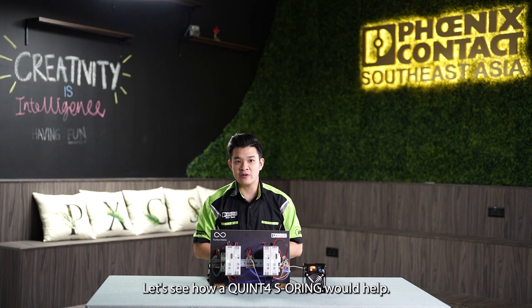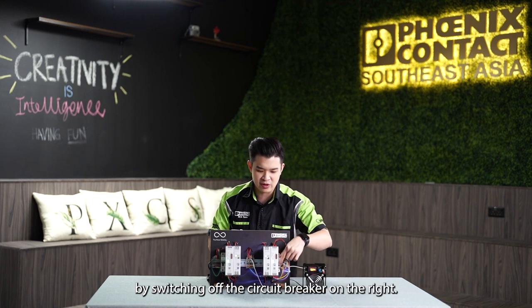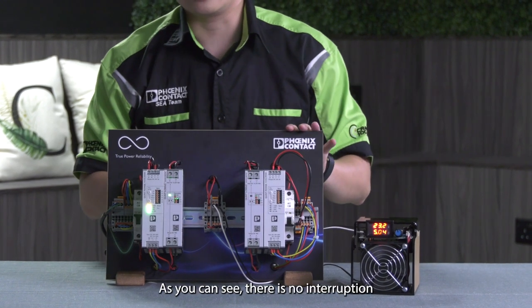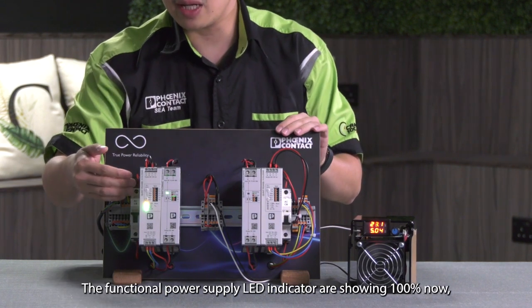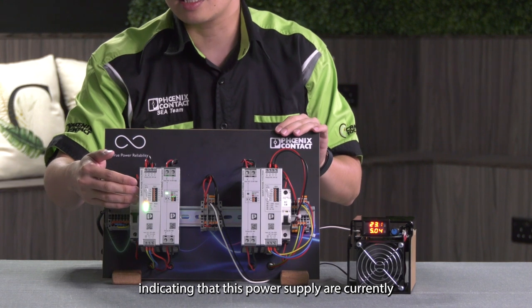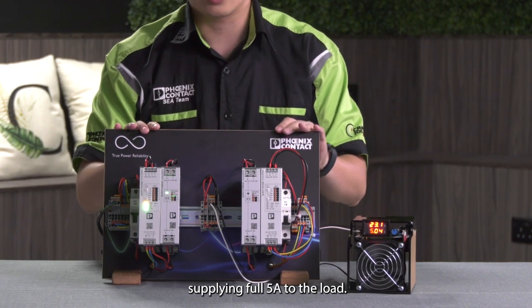Let's see how the QUINT4 S-ORING would help. Let's simulate a power supply failure by switching off the circuit breaker on the right. As you can see, there is no interruption to the operation of the load. The functional power supply is now showing 100%, indicating that it is currently supplying the full 5A to the load.